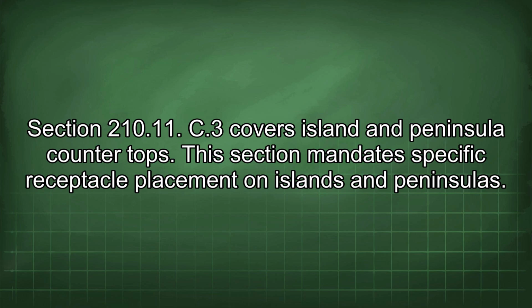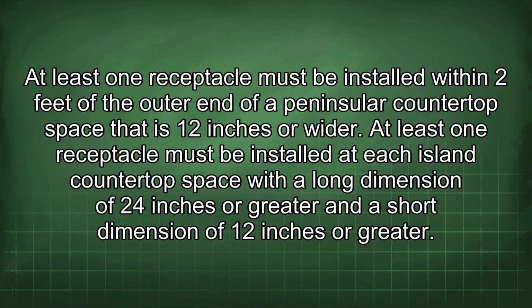Section 210.11(C)(3) covers island and peninsula countertops. This section mandates specific receptacle placement on islands and peninsulas. At least one receptacle must be installed within 2 feet of the outer end of a peninsula countertop space that is 12 inches or wider. At least one receptacle must be installed at each island countertop space with a long dimension of 24 inches or greater and a short dimension of 12 inches or greater.